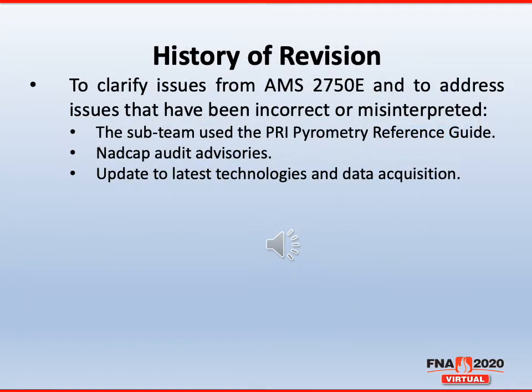When we decided to go to the next revision of AMS 2750, we wanted to make sure that we clarified any incorrect or misinterpreted items that were in the previous specification. We used the PRI Pyrometry Reference Guide. We also used the NADCAP audit advisories that dealt with pyrometry. And obviously we needed to update to the latest technologies and data acquisitions. These AMS specifications are looked at every 5 years, and this was the 5th year for AMS 2750, so it was time for a revision.